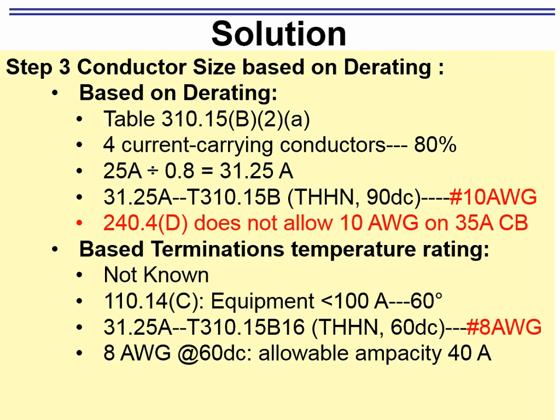All right, so I have four current carrying conductors, which gives me 80%. So I have 25 divided by 0.8, that gives me this number. Since we have THHN, guys, and we're derating, we can go all the way up to where? To the 90 degree column, and now we have number 10.